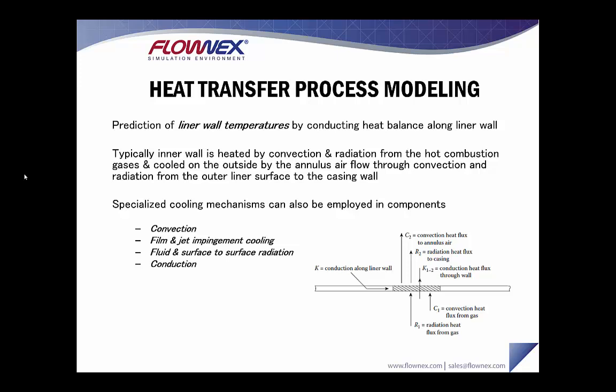Heat transfer process modeling is what allows us to predict liner wall temperatures, and we essentially do this by conducting a heat balance along the liner wall. Typically the wall is heated by convection and radiation from the hot combustion gases, and then cooled on the outside by annulus air flow through convection and radiation from the outer liner to the casing wall. Depending on the liner configuration, several specialized cooling mechanisms may also need to be employed, and I'll go into each of these in more detail in the next couple of slides.